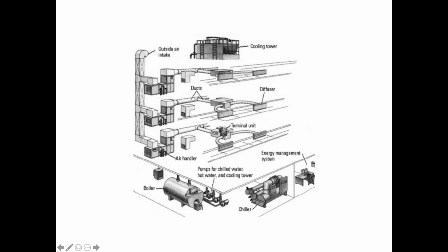You spray it down at the same time that you have these fans running and you're pulling air through that sprayed water. Well, if you pull air through water, through droplets of water, what happens to the water? Some of it's going to evaporate, right? Yeah, you cool it. Some of it is sensible cooling, like it's just the air, cool air hitting it and stuff like that. But most of the cooling comes from evaporation. So when you send that water up to that cooling tower, 99% of that water comes back at 85 degrees. 1% of that water evaporates away, and that's what cools the rest of the water about that 10 or 15 degrees that you need. So that water comes back from that cooling tower at 85 degrees so you can reuse it again. But the only problem is now you've lost that water.